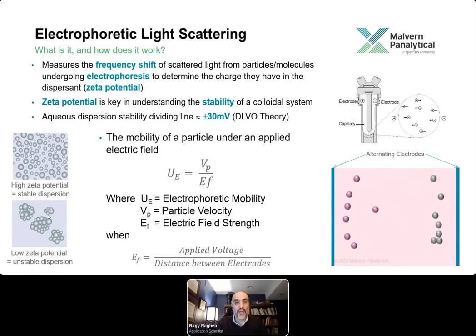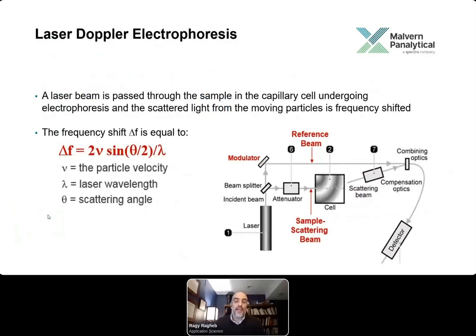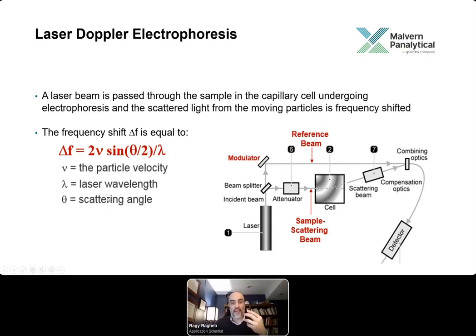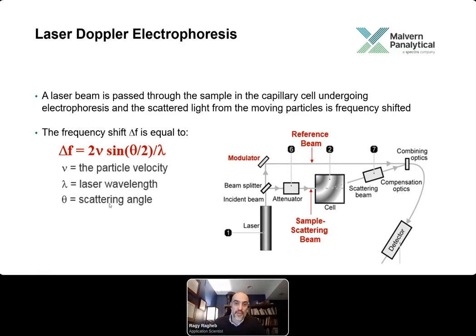The electrophoretic mobility equation involves electric field strength — calculated from the applied voltage across electrodes and the distance between them — and particle velocity. Particle velocity is determined by the laser Doppler effect: looking at a frequency shift between a reference beam and a beam going through the sample. We use this to calculate particle velocity, knowing the 633 nm helium-neon laser wavelength and the scattering angle used to measure zeta potential.